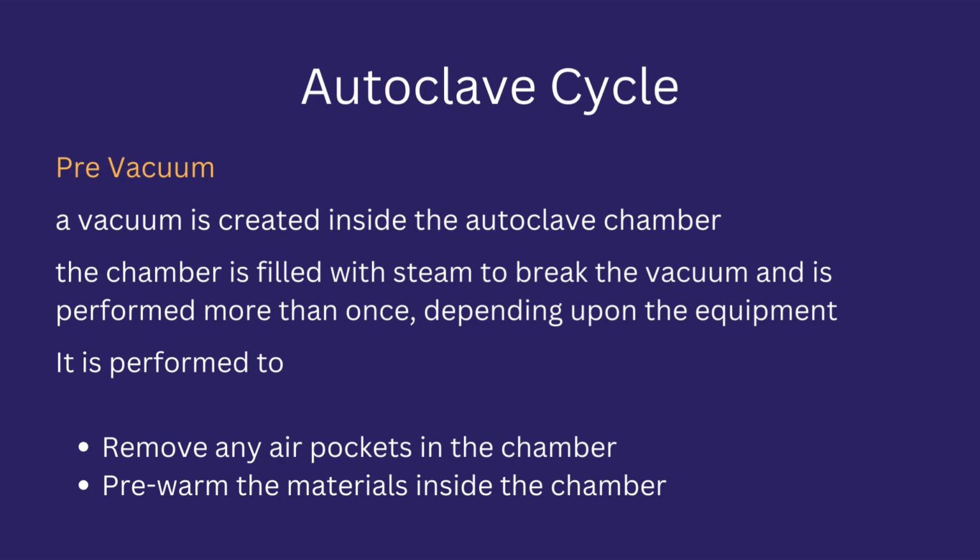And another reason for pre-vacuuming is pre-warming the material inside and to cause a smooth increase of temperature inside.